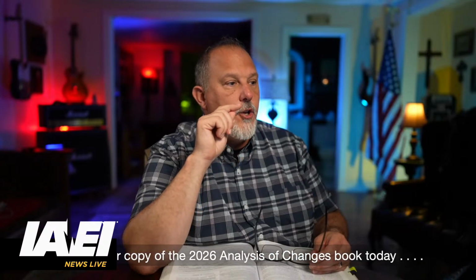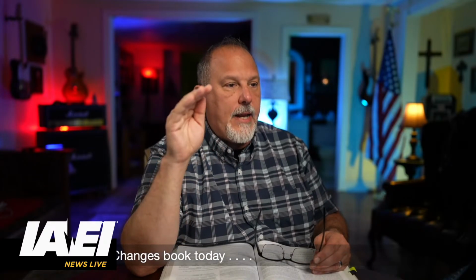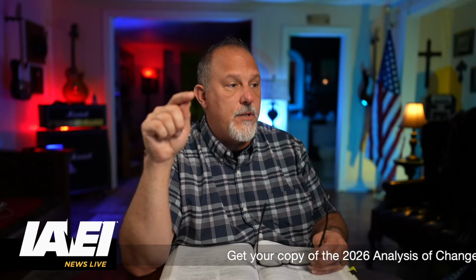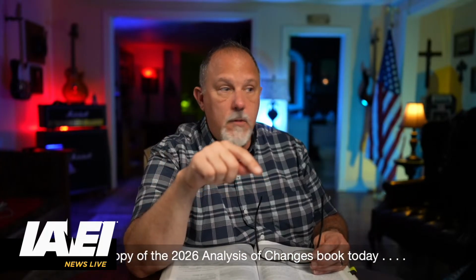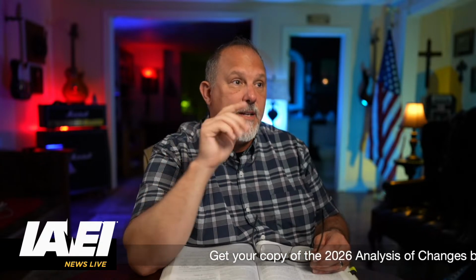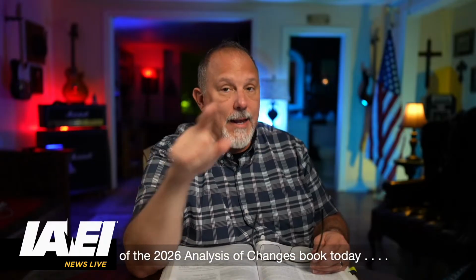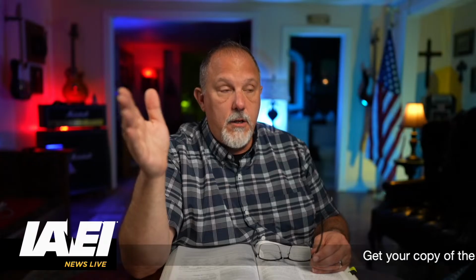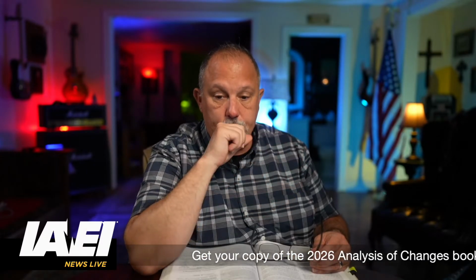And they're saying a higher rating or setting is permitted as long as it doesn't exceed the following. One, the next higher standard rating or setting of fuses and circuit breakers, 1,000 volts and below. And then if it's medium voltage, the next higher commercially available rating or setting for fuses and circuit breakers above 1,000 volts. So I can go to the next higher when it's a medium voltage application, but I can't do that at the 250% for a low voltage transformer. So I think it's a big difference in application of the tables between A and B.